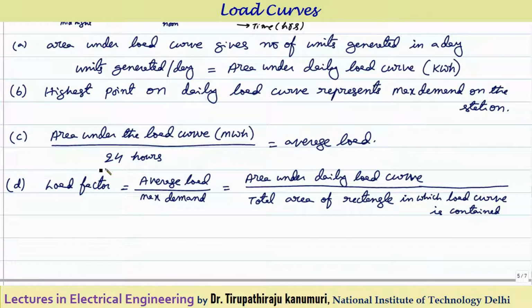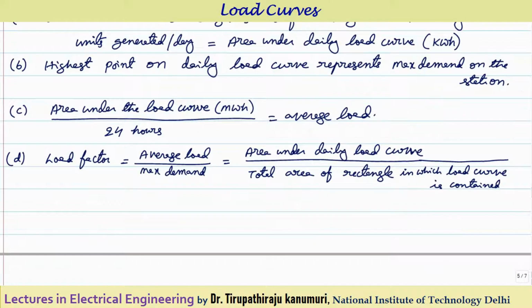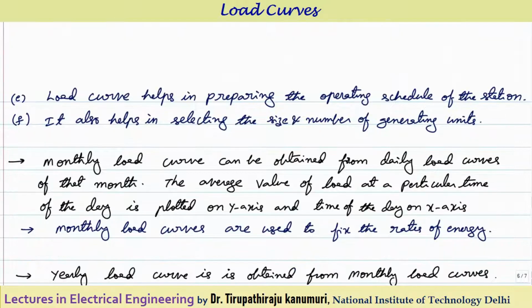That means we can calculate the load factor as the area under the daily load curve divided by the total area of the rectangle in which the load curve is contained. I hope it is clear up to now. Now, the load curve helps in preparing the operating schedule of the station.